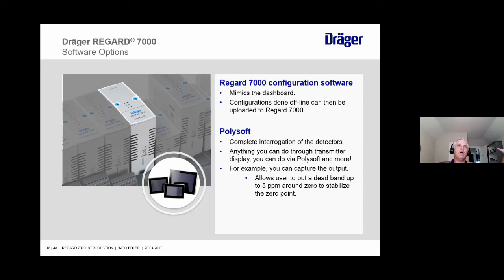I want you to stay on 0. So what does a customer like? A customer wants their transmitters to sit on 0 and send 4 milliamps all the time. So that's the way we can do that. I think that they set the limit at 5 though, because anything above that would probably be a real situation, either positive or negative, that needs to be addressed. But we can help a customer do that. And that's something you can do through Polysoft that you can't do through the transmitter itself. So that's some of the reasons you'd actually want to get Polysoft.